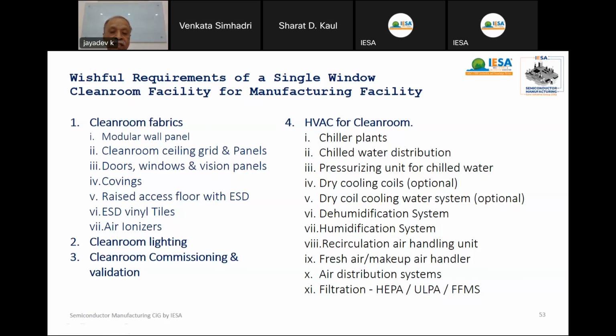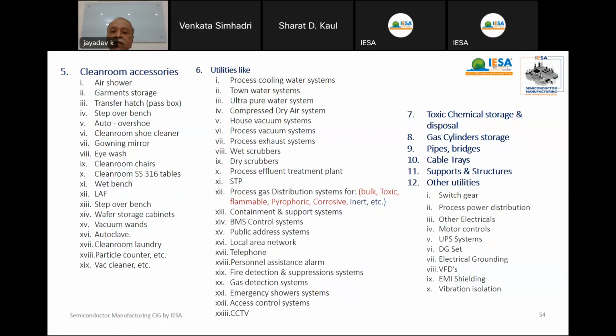Then air distribution we discussed: vertical laminar, unidirectional flow, mixed flow, and then hybrid flow of different types. Particularly, filtration is the heart of the clean room: ultra high efficiency particulate filters, ultra low penetrating air filters, and fan filter module systems. So their efficiency also plays an important role: 99.995% down to 0.2 microns. ULPA filters are 99.995% up to 0.1 microns. These are the HVAC for clean room. Further, the list is very big.